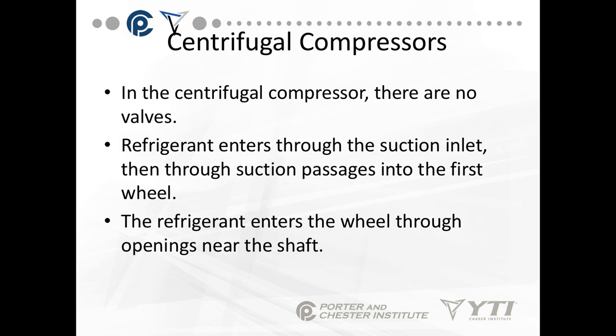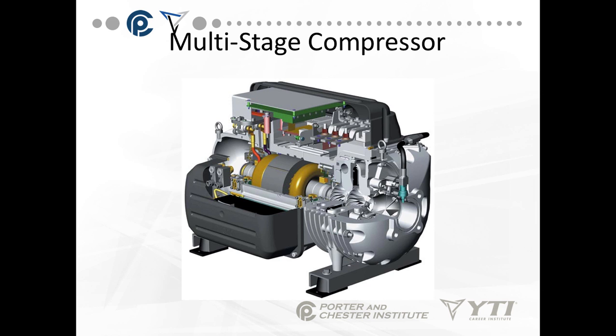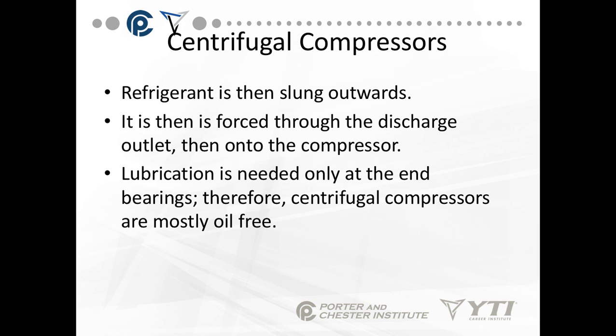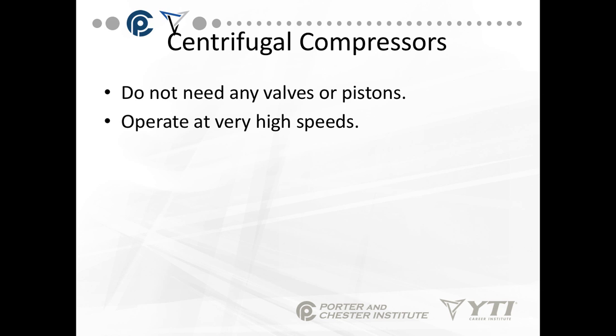In the centrifugal compressor there are no valves. Refrigerant enters through the suction inlet, then through the suction passages into the first wheel, entering the wheel through openings near the shaft. We can have multi-stage designs. Refrigerant is then slung outward and forced through the discharge outlet to the condenser. Lubrication is needed only at the end of the bearings, so centrifugal compressors are mostly oil-free — another plus for a large system. They do not need any valves or pistons, and they operate at very high speeds, so proper maintenance makes a big difference.